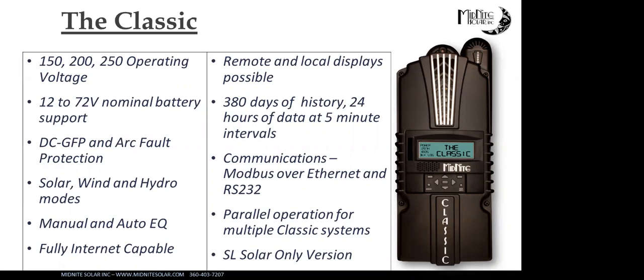Manual or auto EQ. One of the nice features of the auto EQ on the Classic is it does have a function called retry days. So if you tell it to EQ every 30 days and then retry for 3 days, on day 30, it will start an EQ charge. And if it's cloudy or something and it doesn't accomplish it, it'll try again the next day, and it'll try again the next day. So that's kind of a neat function. Along that same avenue, but completely backwards and different, it also has a function called skip days. And skip days, what that does is it ignores the bulk absorb cycle and goes directly to float. So let's say you've got a big lead acid battery bank, a whole bunch of PV, and very minimal loads, or you've got a camp that's unattended a lot of times.